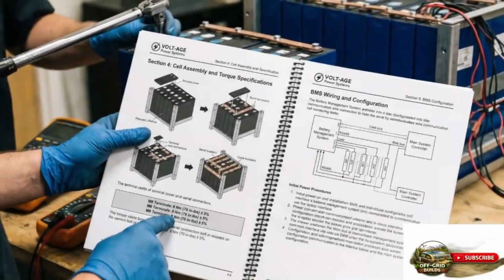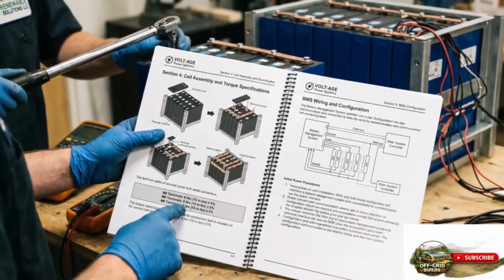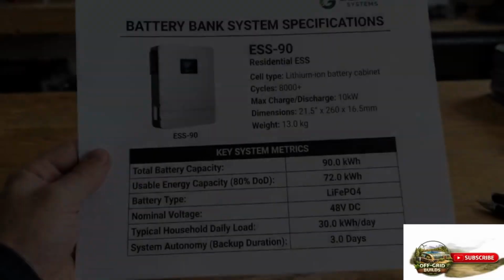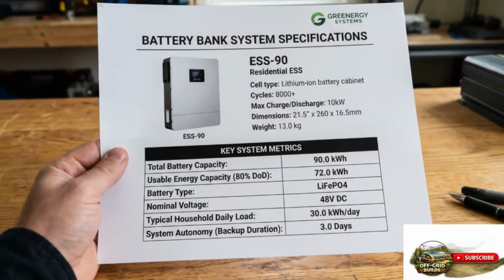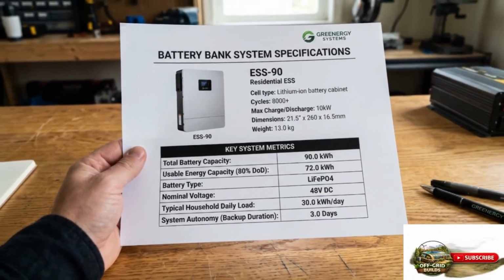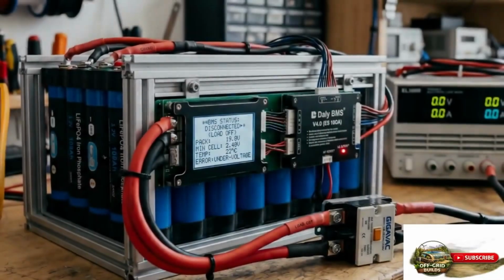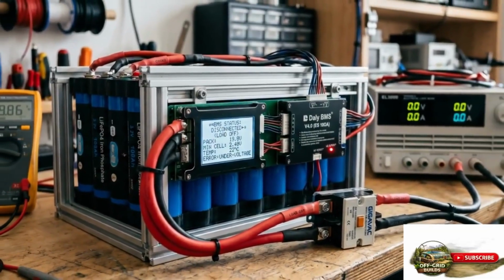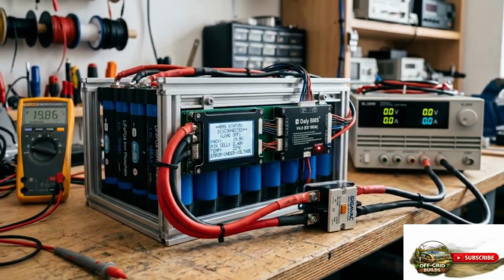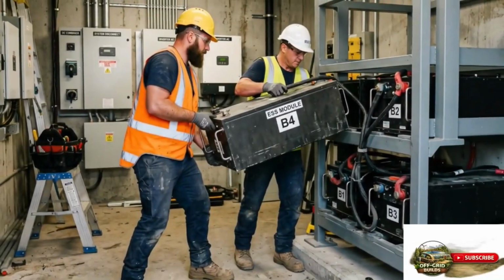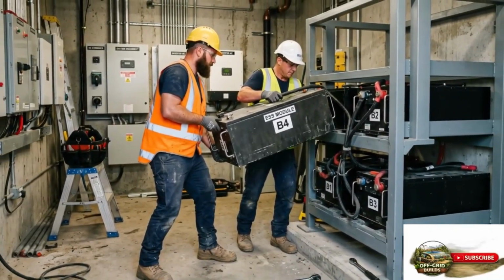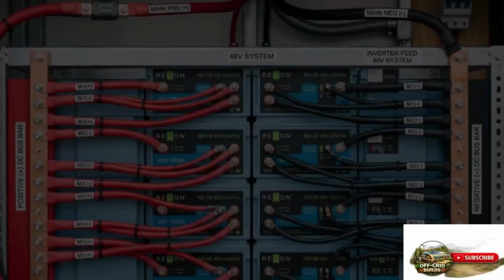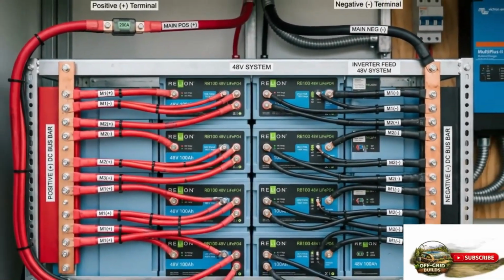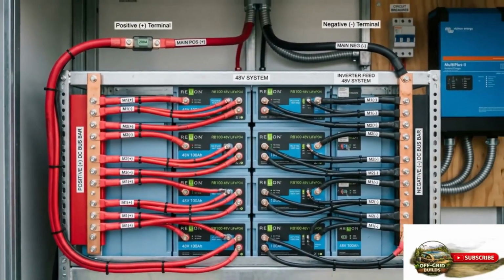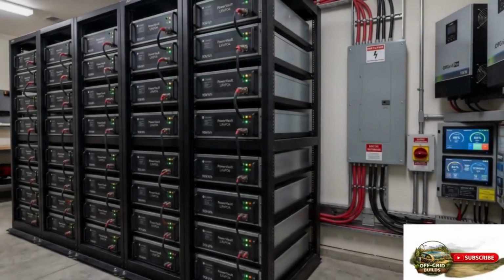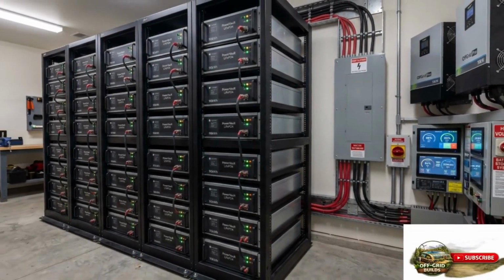At 48 volts, which is the standard system voltage for most large residential off-grid systems, configuring lithium iron phosphate cells requires connecting cells in series to reach the nominal battery voltage. Lithium iron phosphate cells have a nominal voltage of approximately 3.2 volts per cell. A 48-volt battery bank requires 16 cells in series to reach the nominal system voltage of 51.2 volts. Multiple 16-cell strings can be wired in parallel to increase the total capacity of the battery bank.